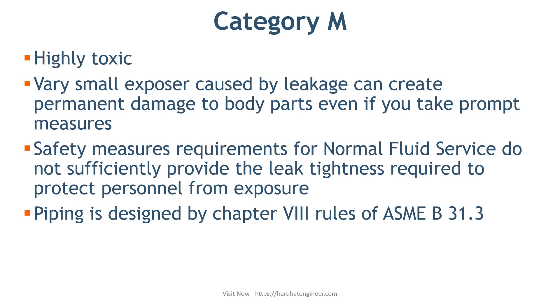The second fluid service is Category M. Category M fluid is highly toxic. Very small exposure caused by leakage can create permanent damage to body parts even if you take prompt measures. All such fluids, and if the owner of the facility — based on his experience — feels that safety measures required for normal fluid service do not sufficiently provide the leak tightness required to protect personnel from exposure, are part of this group. Category M fluid service piping is designed by chapter 8 rules of ASME B31.3, so you must take enough safeguarding while designing piping for Category M fluid services.